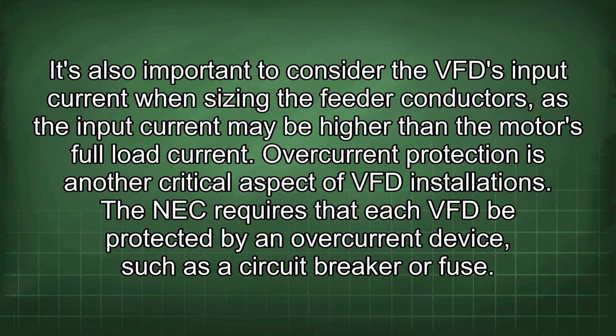It's also important to consider the VFD input current when sizing the feeder conductors, as the input current may be higher than the motor's full load current. Overcurrent protection is another critical aspect of VFD installations. The NEC requires that each VFD be protected by an overcurrent device such as a circuit breaker or fuse.